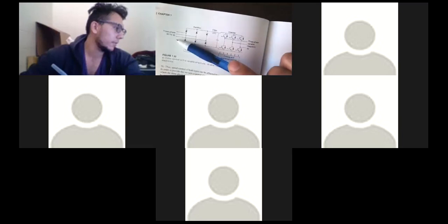The computer can just turn on those switches. Every one of those is a switch. If you look closely, there are 6 switches over here, those are the diode switches. How about the inverter? The inverter is another 6 switches. That's all we need, 6 switches. By computer control of exactly when to turn on those switches, almost like magic, the input is converted to DC, and then DC is converted to variable frequency.